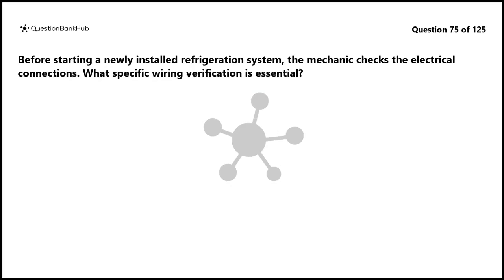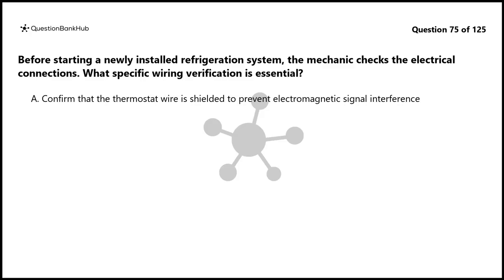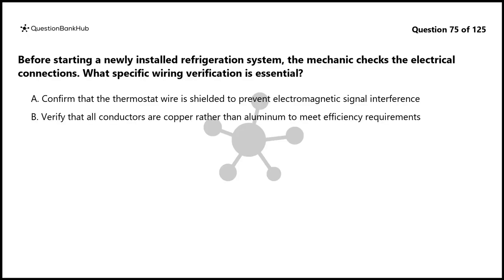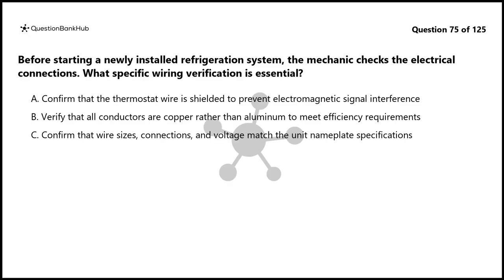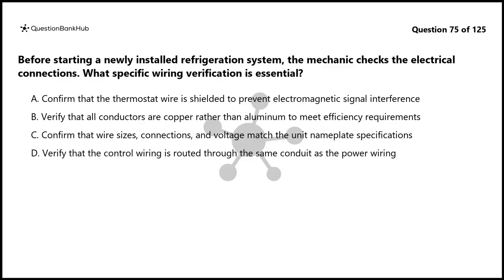Question 75. Before starting a newly installed refrigeration system, the mechanic checks the electrical connections. What specific wiring verification is essential? A. Confirm that the thermostat wire is shielded to prevent electromagnetic signal interference. B. Verify that all conductors are copper rather than aluminum to meet efficiency requirements. C. Confirm that wire sizes, connections, and voltage match the unit nameplate specifications. D. Verify that the control wiring is routed through the same conduit as the power wiring.